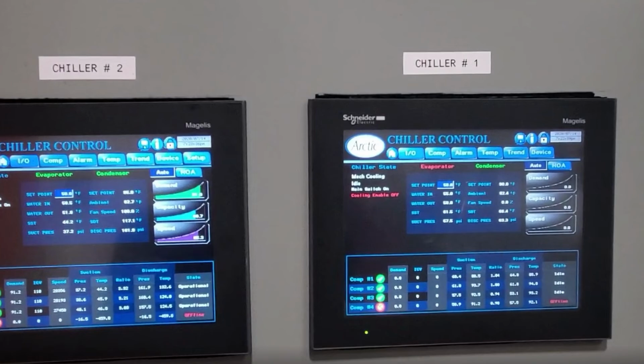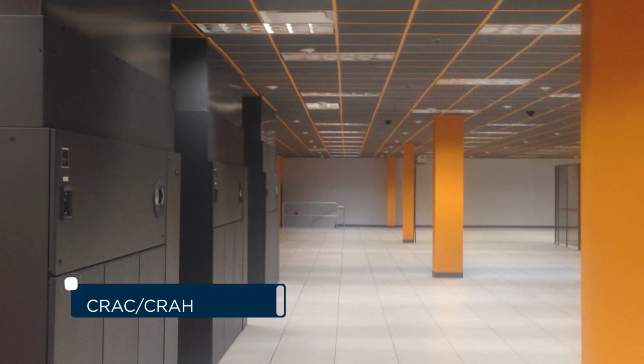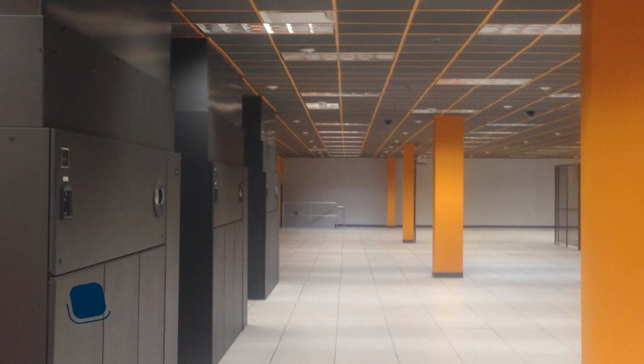The data hall is configured with chilled water cooling and DX cooling, CRAC and CRAH units along the outer edges and middle of the room. The CRAC and CRAH units are powered by a primary and secondary feed, which are both backed up by generators. With all that power, we need to cool your infrastructure. So let's move on to cooling. This site employs 40-ton CRAH units and 30-ton CRAC units.